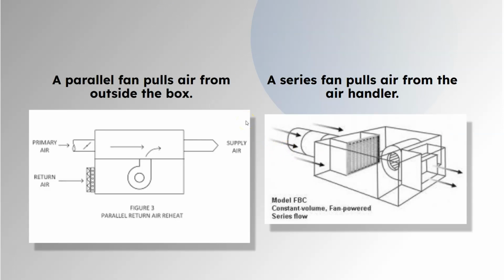When you have a fan, there's two different types of fan power box. There's a parallel box and a series box. A parallel is going to pull air from outside the VAV and push it out when based on temperature, right? This is only going to come on in heat mode. So we're going to close off the damper, turn on the fan power box, and now instead of pulling 55-degree air from the air handler and heating it up with the reheat, we're going to pull attic air, might be 60, 70 degrees, and warm it up. So we'll get a lot warmer air coming out of here after it goes through the heat strips, if there are heat strips. Most of the time, a fan power box doesn't have heat strips.